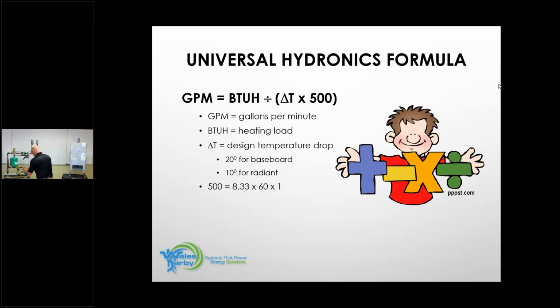So let's just assume this is my boiler and it's a full water system, no antifreeze. Every gallon of water that I run through this boiler and send out of here has the ability to carry a delta T times 500. Cast iron boiler, 20-degree delta T times 500 equals 10,000. So that tells me every gallon of water, thank you, Jim, every gallon of water within this boiler has the ability to absorb 10,000 BTU. Every gallon of water within this system has the ability to absorb that BTU.